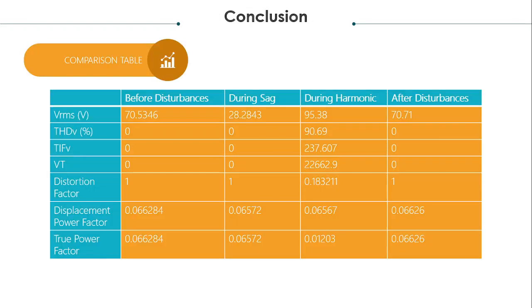And then, the power quality indices are being measured and analyzed on the implemented system along with the RLC load before any disturbance, during sag, during the harmonic distortion, and after these disturbances. Some of these power quality indices were generated directly through LabVIEW blocks, others were designed using mathematical blocks to perform the right operations. These measures are displayed in the following table to clearly analyze how the parameters are affected by each disturbance. This table indicates that the RMS value is affected by all types of disturbance.